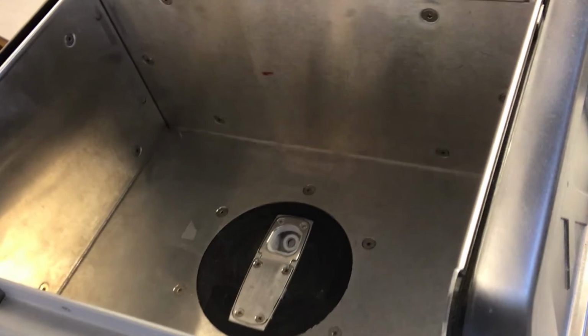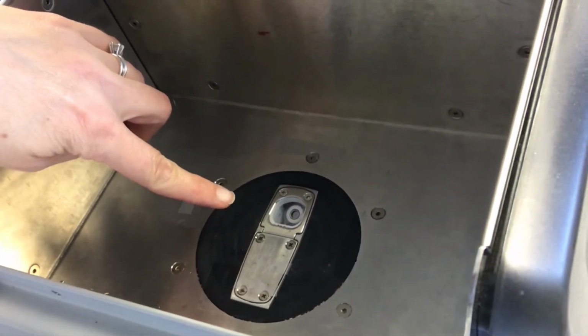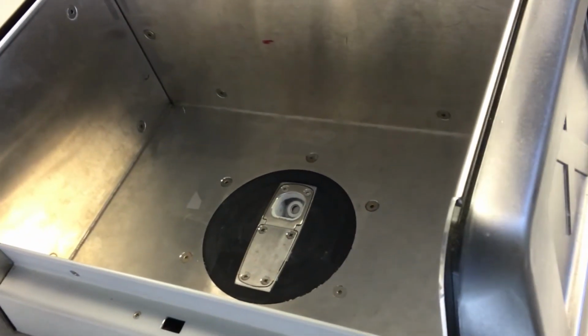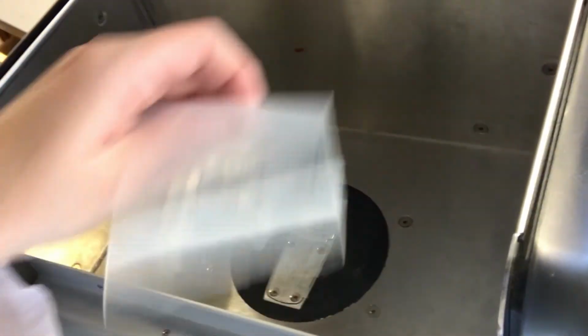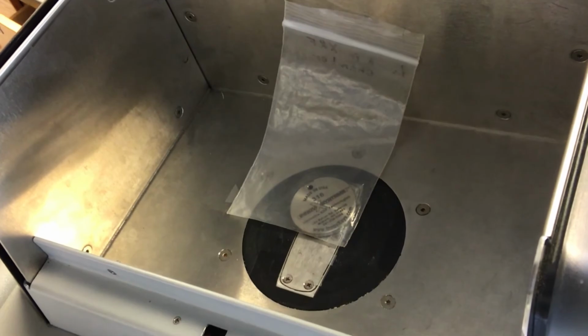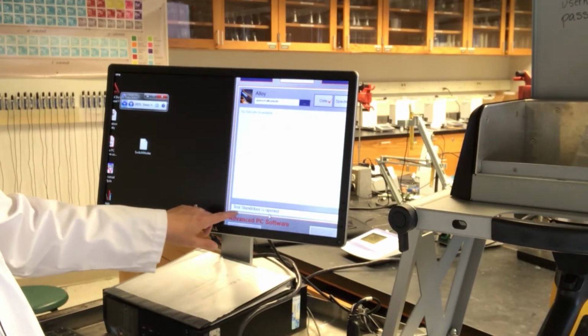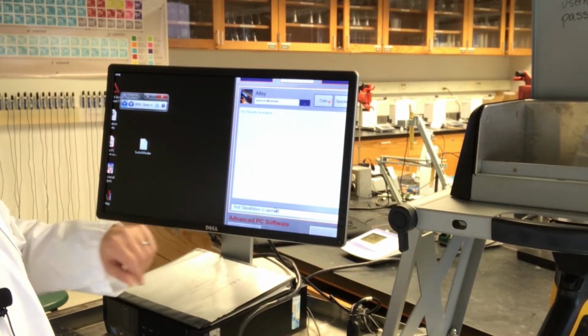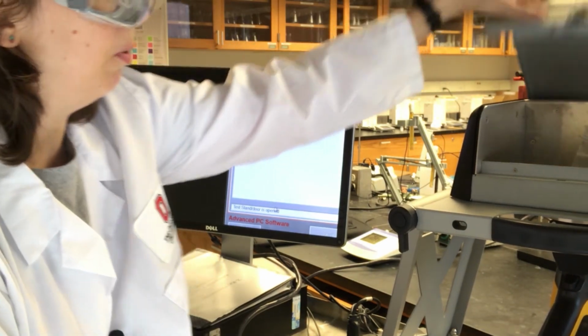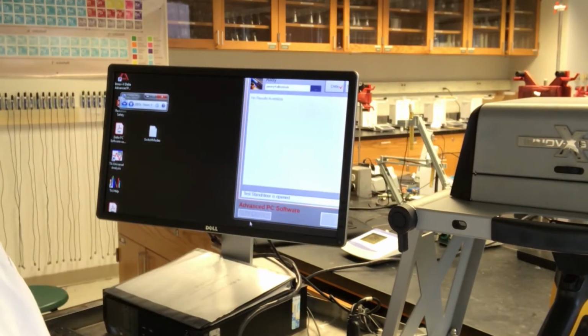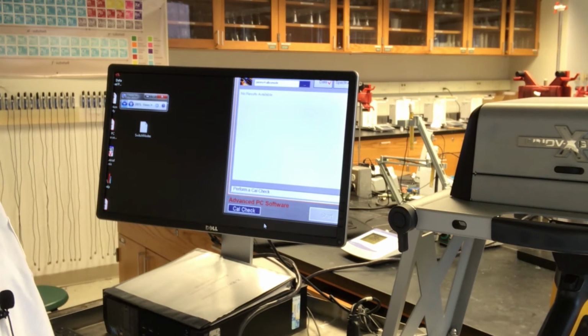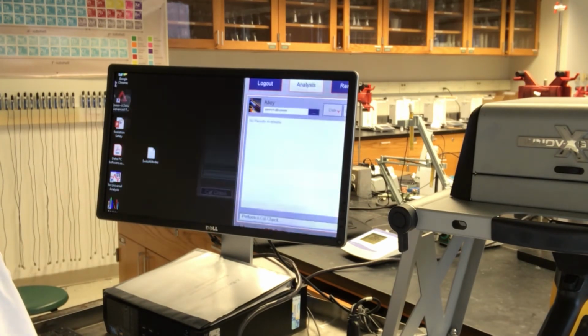Okay, so this little window is where the X-rays are emitted and where detection occurs after impinging on the sample or calibration disc. So it's going to go in there like that. And you can see, maybe you can see, here it says the test stand is open, so the instrument will not run. Now we close that, and the cal check button is now accessible, so clickable. So we'll click that.